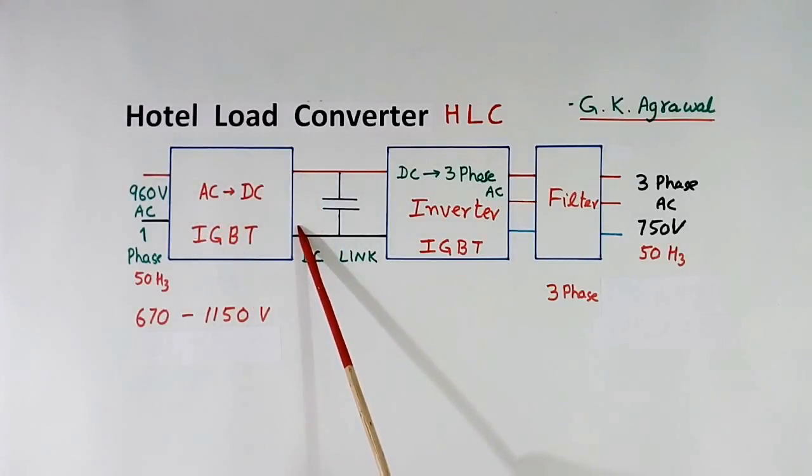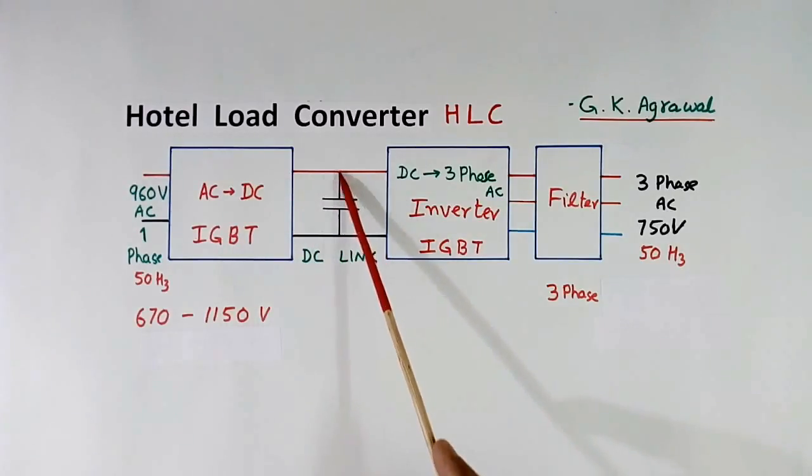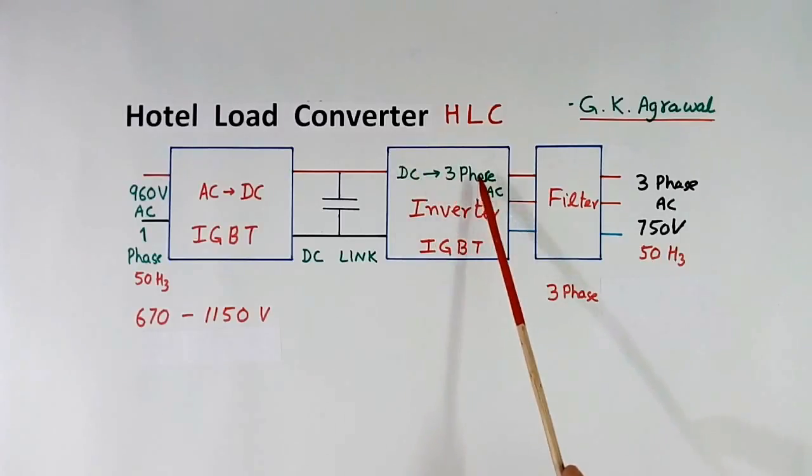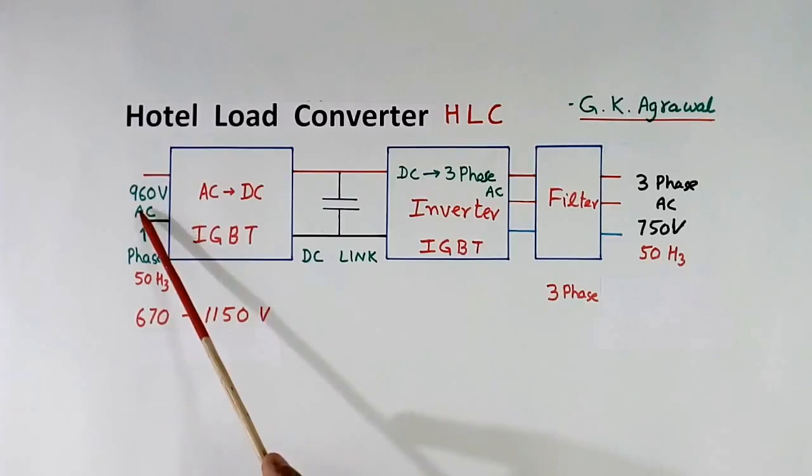This is IGBT based. This is DC link, there is a capacitor which is charged. This inverter converts DC into 3 phase AC. So we get AC here, but this has harmonics, so we require a filter. And here we get less harmonics. So output will come 3 phase AC 750 volt 50 hertz supply. So this hotel load converter converts 1 phase AC 960 volt into 3 phase AC 750 volt 50 hertz.